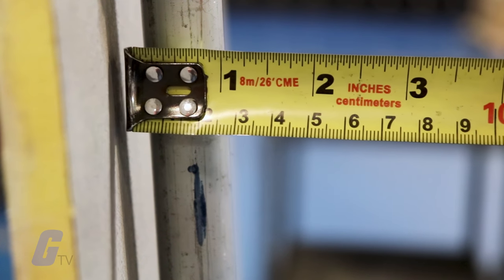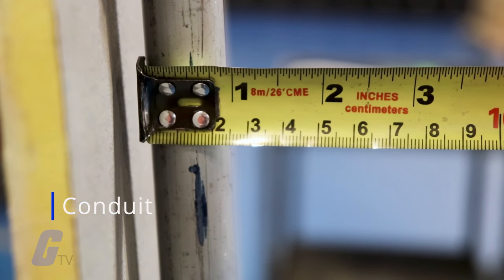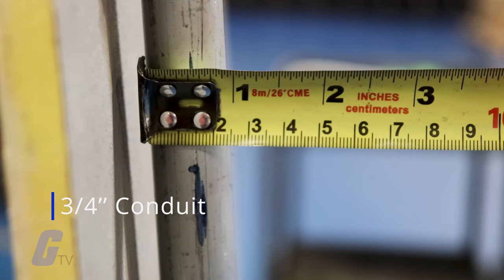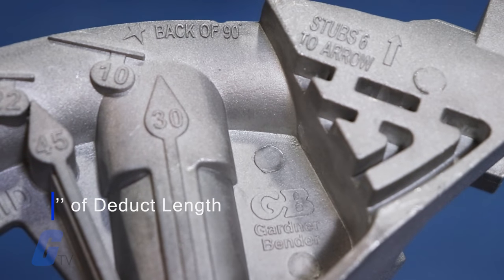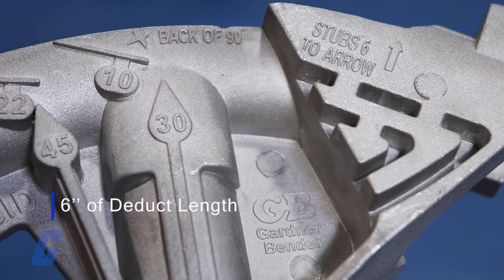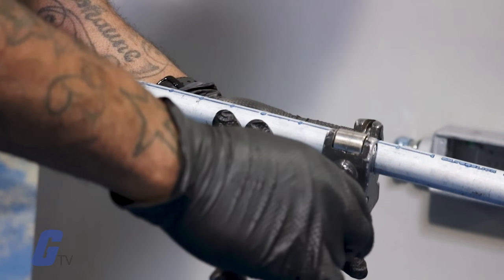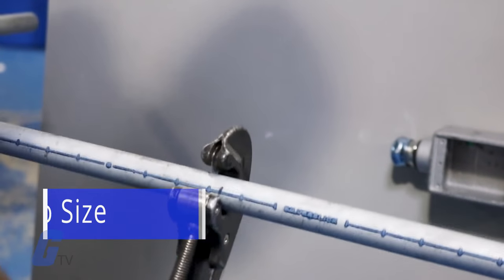This amount varies depending on the diameter of the conduit you are using. For a 90 degree bend, a ½ inch conduit requires 5 inches of deduct length. A ¾ inch conduit requires 6 inches.